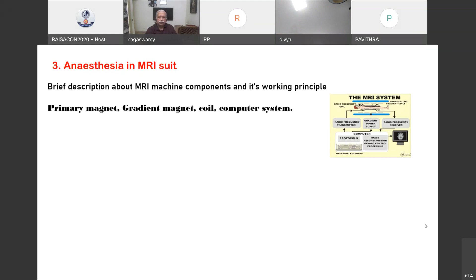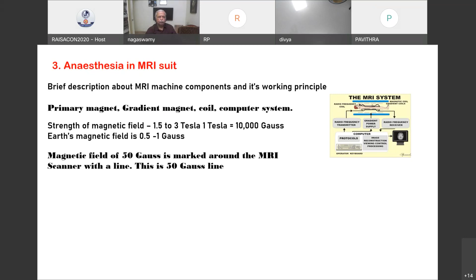And the strength of the magnetic field: these are points which I have mentioned for your practical viva exam, where they may ask you what is the strength of the magnetic field, 1.5 to 3 Tesla. If you see MRI lab advertisements, they will say we have a 1.5 Tesla, we have a 3 Tesla machine. 3 Tesla is very, very powerful, not commonly used. 1.5 is very common. And 1 Tesla is equal to 10,000 Gauss. The Earth's magnetic field is only 0.5 to 1 Gauss. A magnetic field of 50 Gauss is marked around the MRI scanner with a line. This is called the 50 Gauss line. You can see in this picture, the orange line surrounding it is the 50 Gauss line.